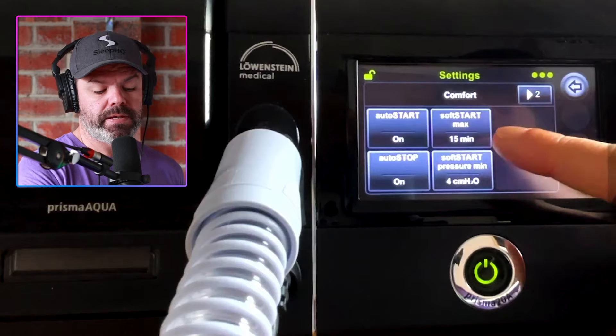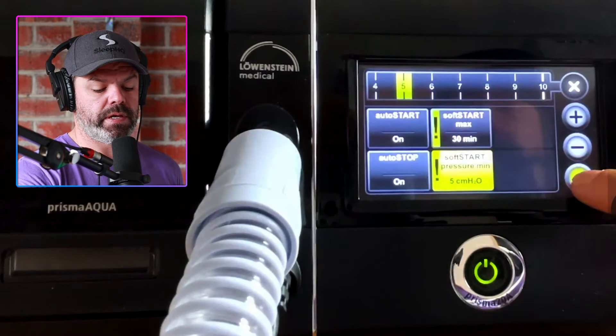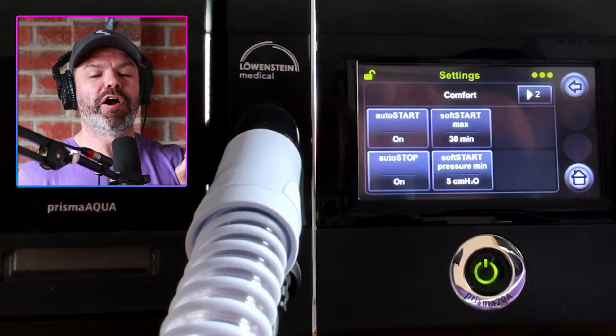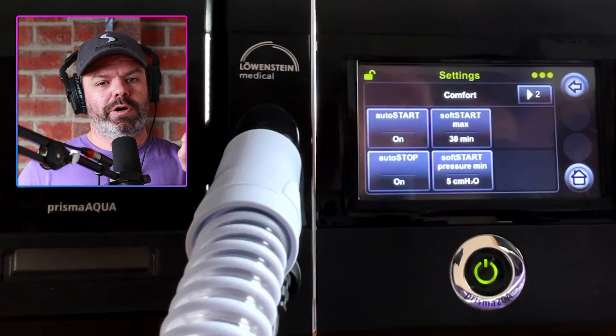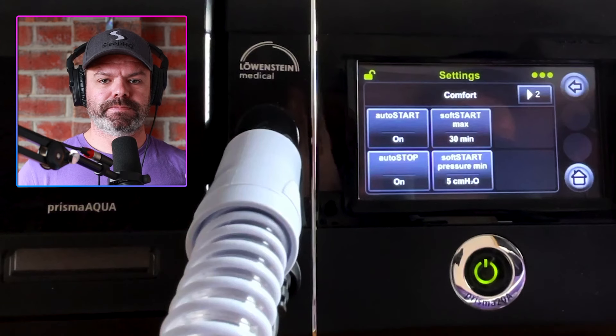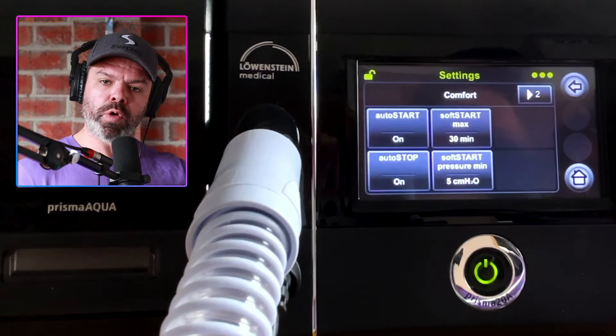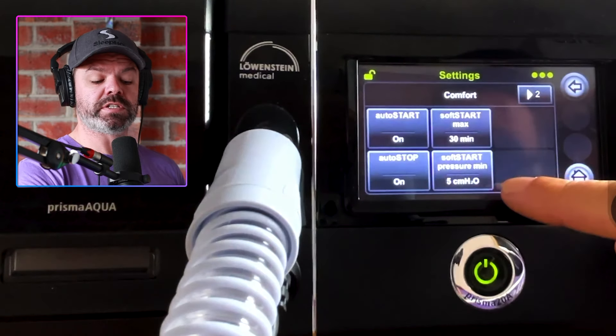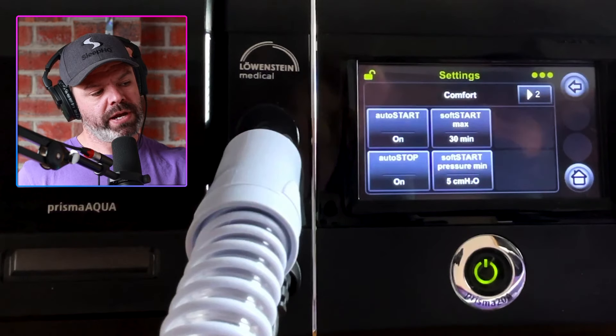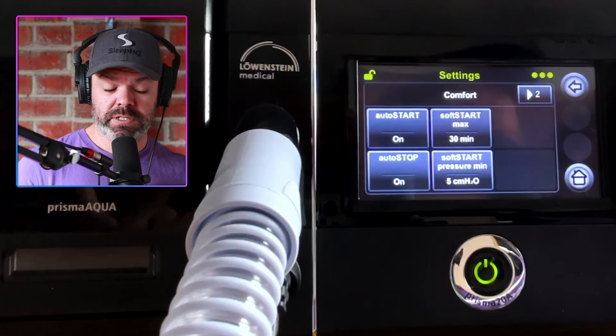Soft start max and soft start pressure min — this is like a ramp period. I'll set soft start max to 30 minutes and the soft start pressure to 5 centimeters. Our P-max and P-min were 16 and 10, so 10 was the lowest level. In bed while drifting off, 10 might feel too high, so we set the ramp to start at 5 centimeters and over 30 minutes it gradually increases up to the P-min of 10 to help you get off to sleep.